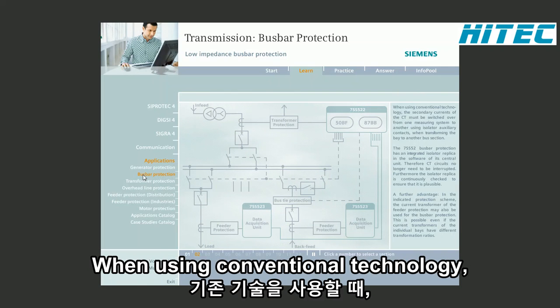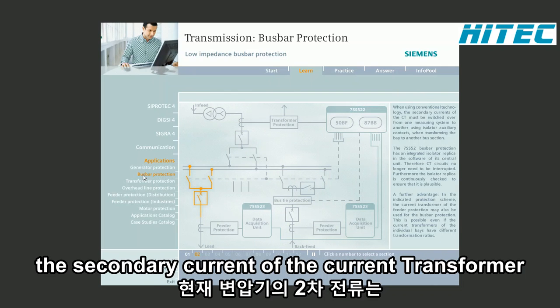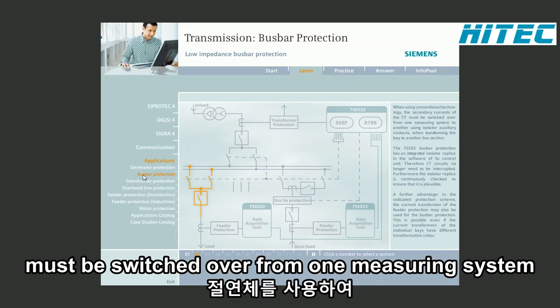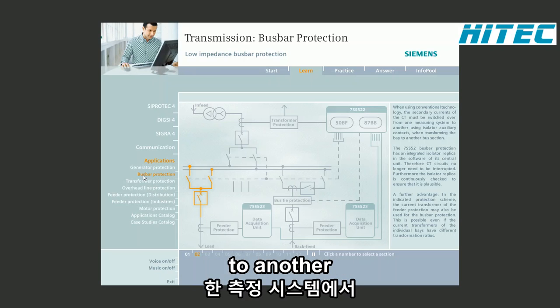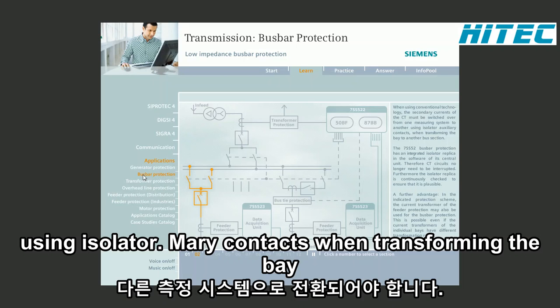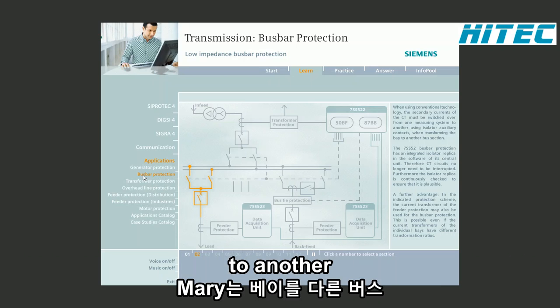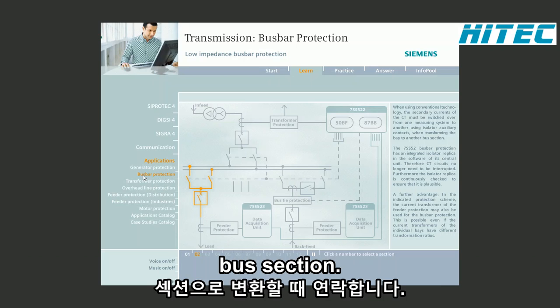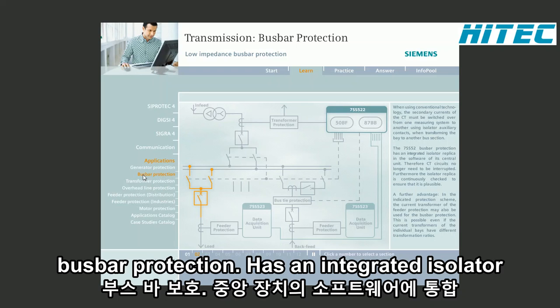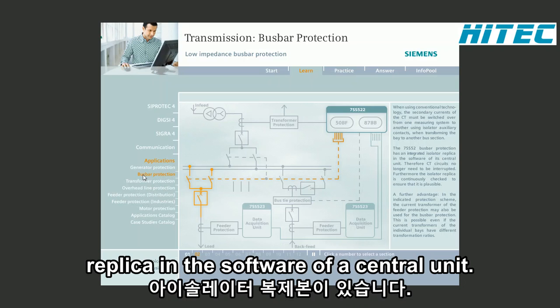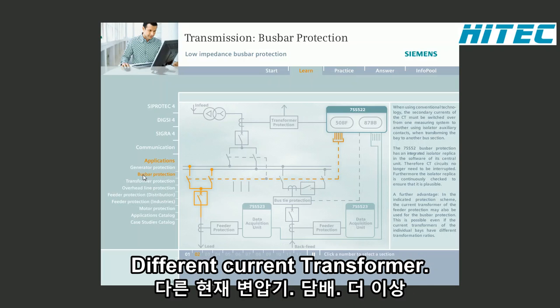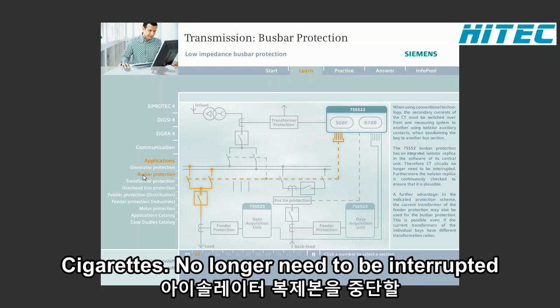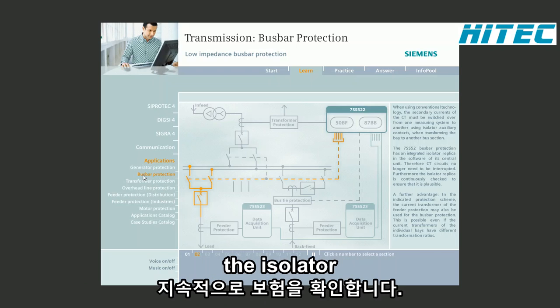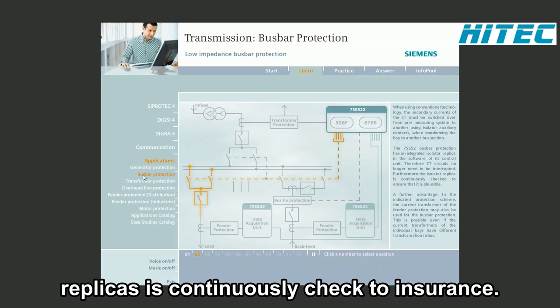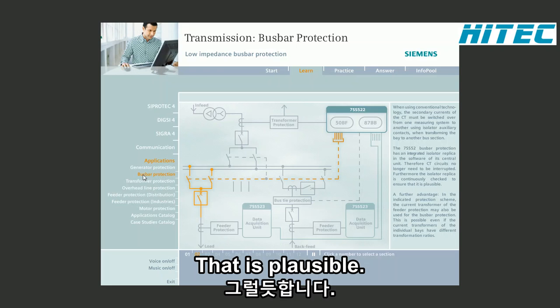When using conventional technology, the secondary currents of the current transformer must be switched over from one measuring system to another using isolator auxiliary contacts when transforming the bay to another bus section. The 7SS52 busbar protection has an integrated isolator replica in the software of its central unit. Therefore, current transformer circuits no longer need to be interrupted. Furthermore, the isolator replica is continuously checked to ensure that it's plausible.